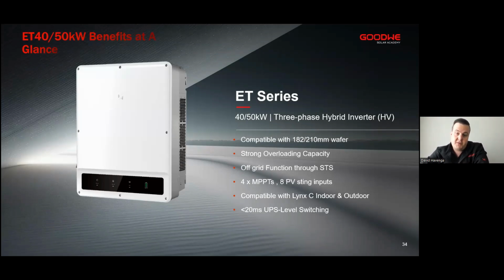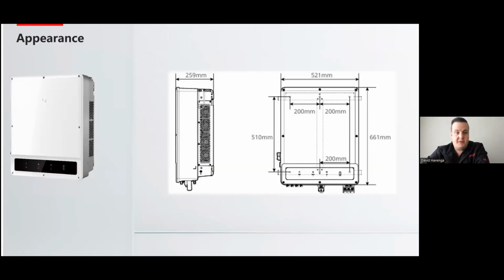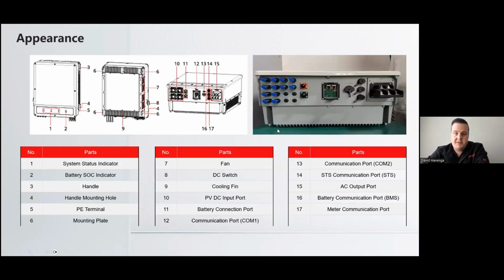For off-grid and backup operation, we have an extra component called the STS. The 50 kilowatt has 4 MPPTs with 8 strings, and it's compatible with our Lynx C indoor and outdoor batteries. As with all of our products, we have the same white metallic color. You'll see this unit is very compact for a 40 or 50 kilowatt device. Below we can see an example of a 40 kilowatt unit. The 40 kilowatt has 3 MPPTs, where the 50 will have 4 MPPTs. We also have one singular battery connection on the device. We have our multi-port connector for parallel, as well as a bunch of other features in the inverter, and then all of our COM ports.